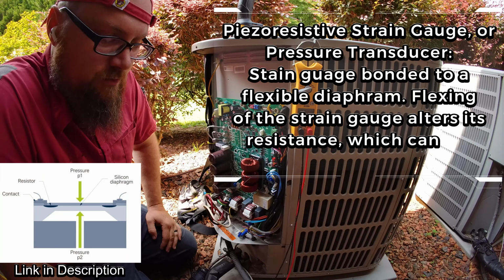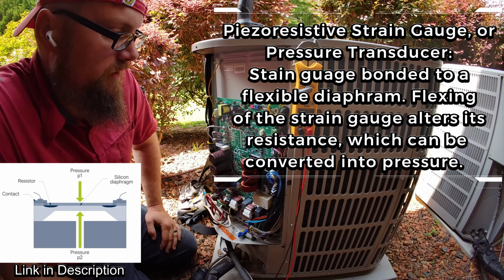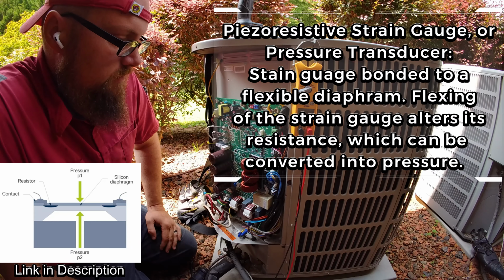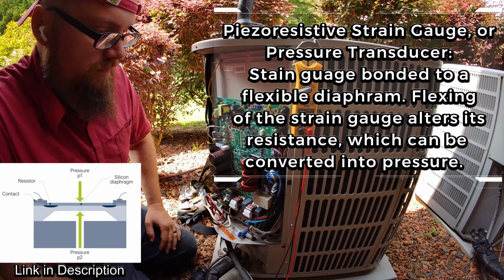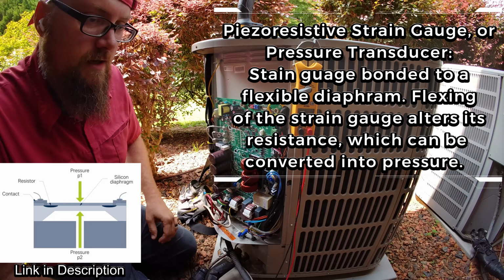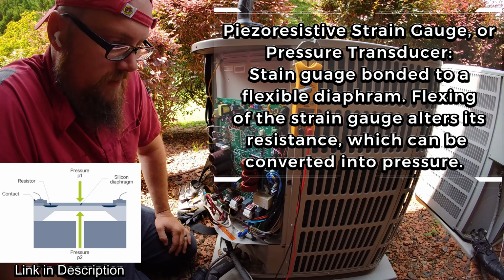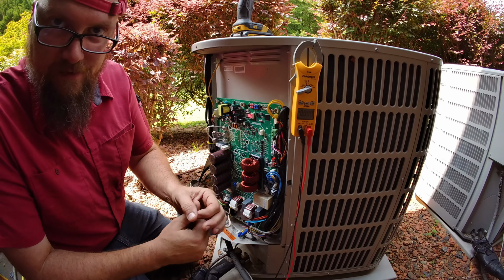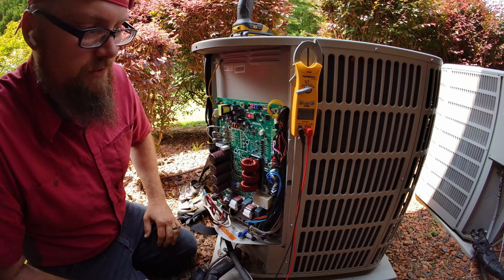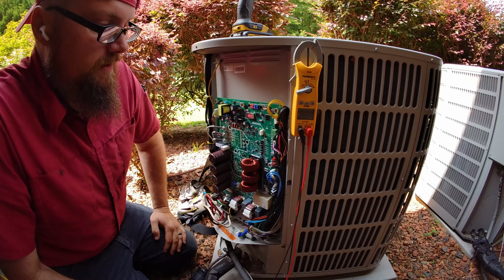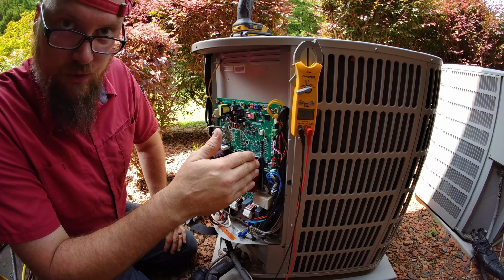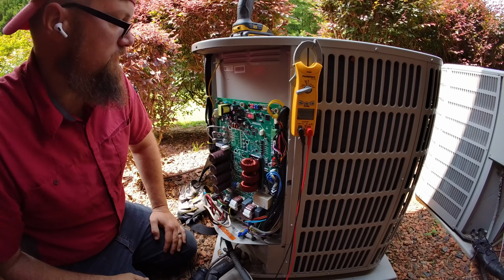What this transducer is actually doing is, I believe it's a piezoelectric, or piezoresistive rather, little tension gauge essentially. So we've got a diaphragm pushing up against it, and as that little piezoresistive piece deforms, stretches, moves a little bit, it changes the resistance in it, and that will give us a pressure reading once you calculate how much voltage you get through it.